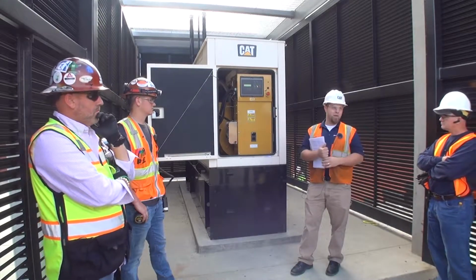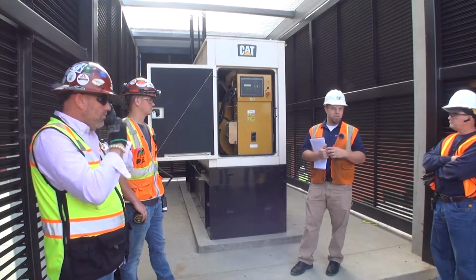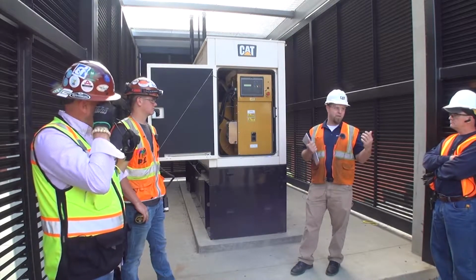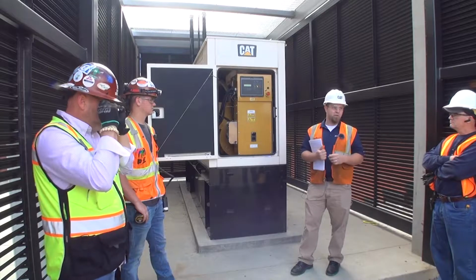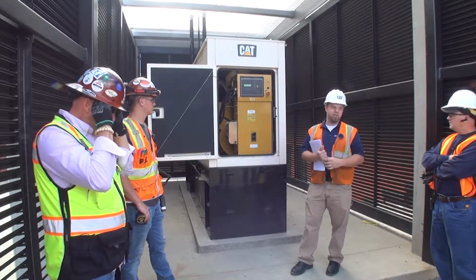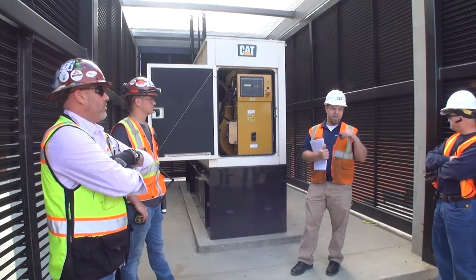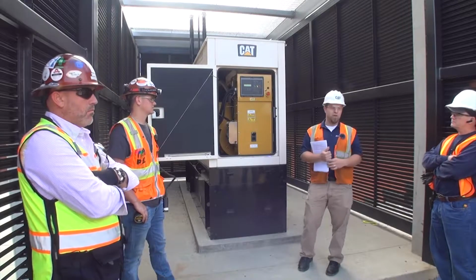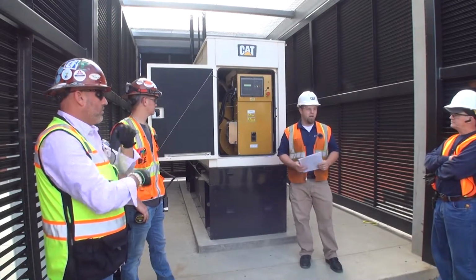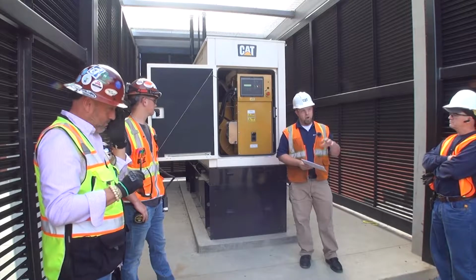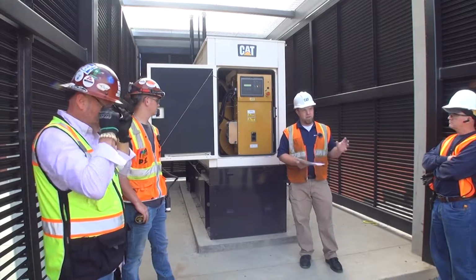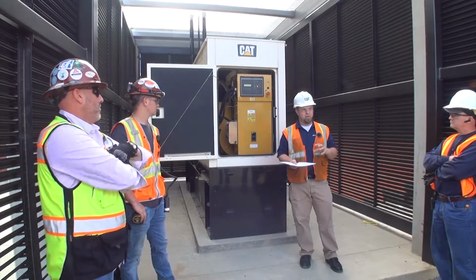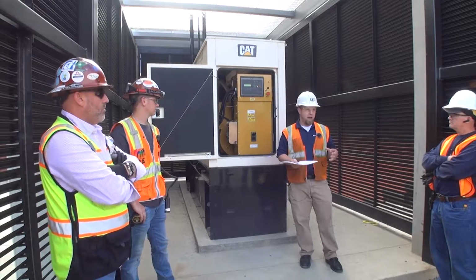I know that because I've been a technician and had a unit shut down at 3 hours 45 minutes, and had to start the test all over again. It has to be 4 hours seamless. If the fire marshal catches it, they will make you redo it. So food for thought—that's why it's important to know what your monthly transfers are, because it might save you from having to do more service than you really need to.